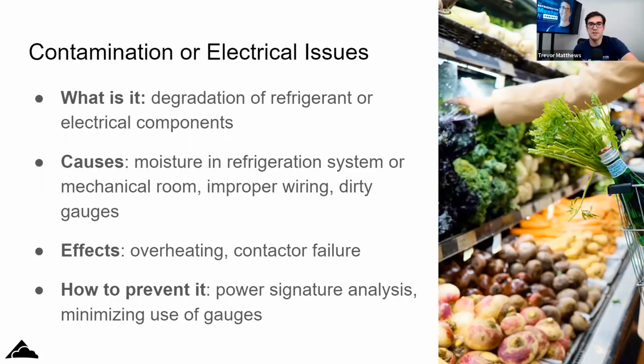The largest percentage is from mechanical failures. So from what we talked about already: floodback, flooded starts, slugging, oil issues, contamination. That's what causes electrical issues. There's only 20% of the time there's a true electrical issue from the grid or from the contactor or whatever. Most of it is from mechanical failure.